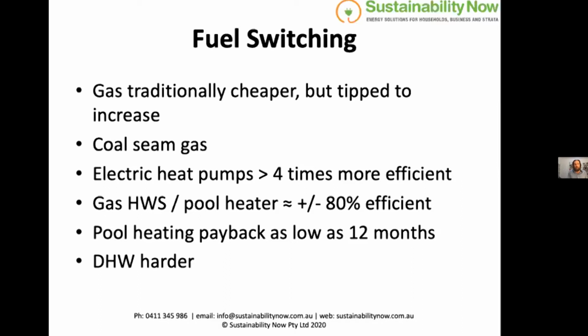And it's just more efficient, I suppose. Electric heat pumps can be greater than 4 times more efficient than an equivalent gas heater. So you might have a coefficient of performance of 4 or up to 5 for an electric heat pump versus maybe 0.8 for a gas heater that just loses energy. You'll never get more than the same number of watt hours or kilowatts or megajoules in and out. Pool heating: switching your gas or electric element heater to an electric heat pump can pay for itself in as low as 12 months, but up to 3 years as well. Domestic hot water: converting your large gas domestic hot water system to a heat pump is a little bit harder, but we won't go into the detail of that.